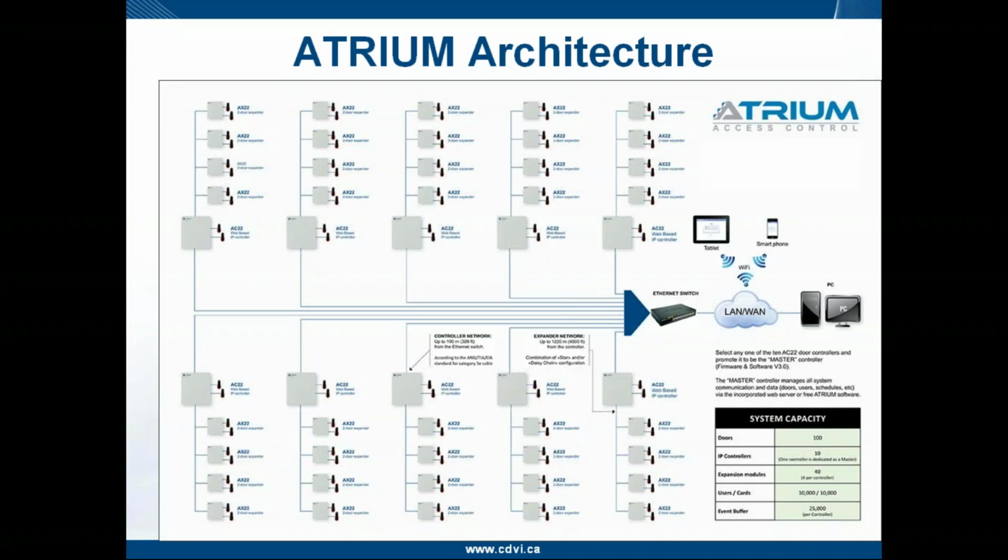However, if this door is an expander door and it has now gone offline, say someone cut the Cat5 cable between the expander and the control panel it's connected to, both doors on that expander will lock down. So the schedule does not exist. There's no unlock schedule.